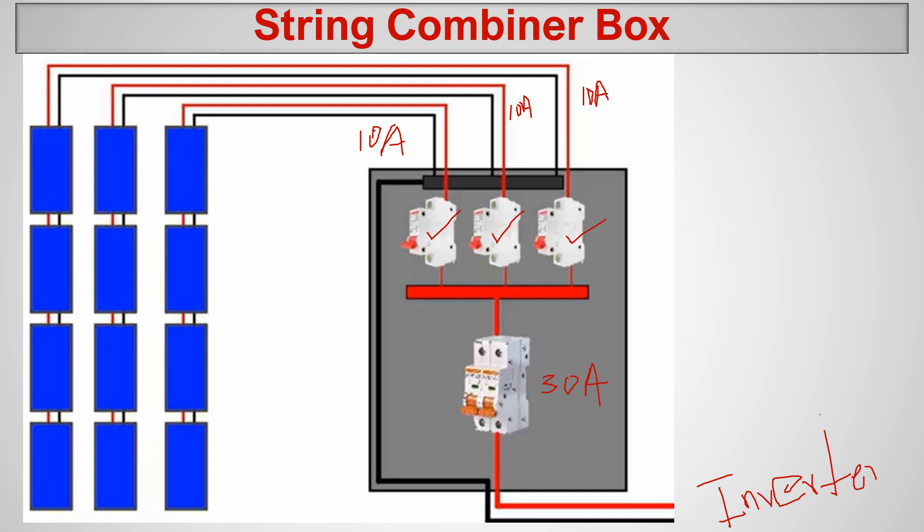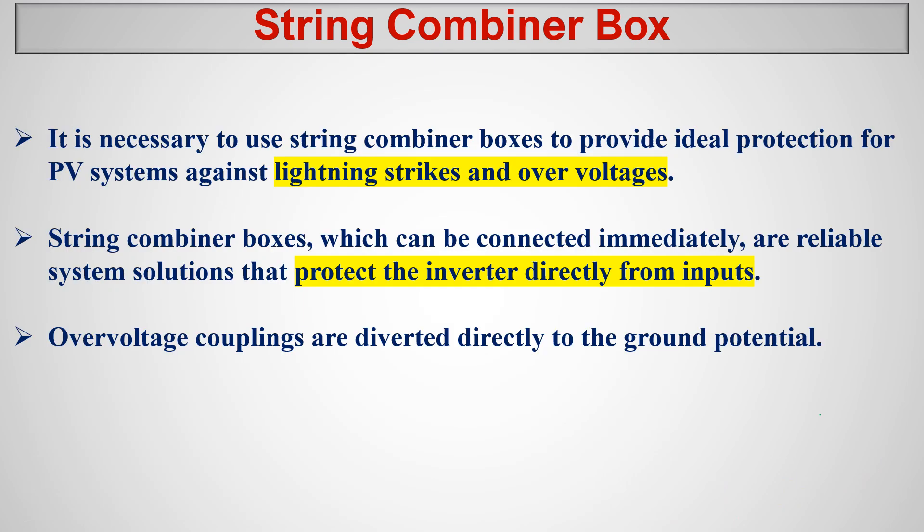This is how the system works. Basically, inside the combiner box we combine the three strings together while also having a safety system — the circuit breakers. The primary function is combining, and the second function is installing protection devices inside the combiner box. In some installations they separate the circuit breakers into another box, but in most cases both are combined together in the string combiner box.